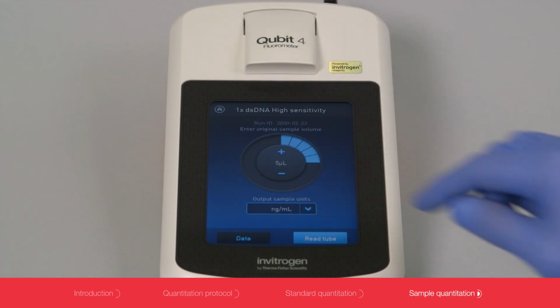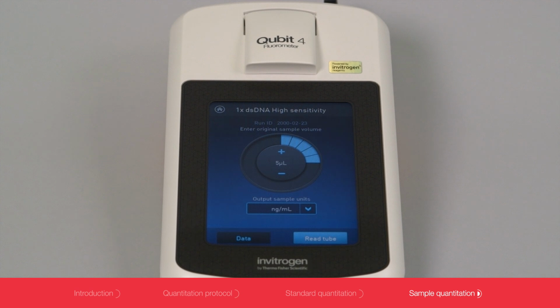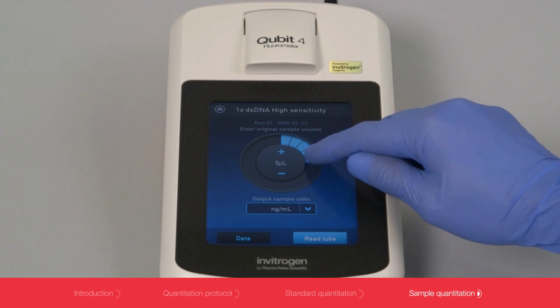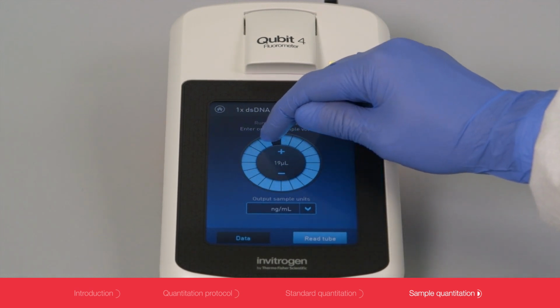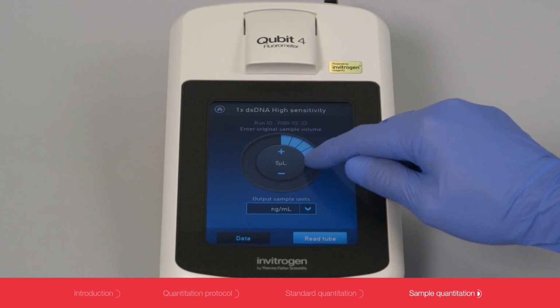After pressing the Run Sample button, a screen will appear that will ask for the amount from your original sample that you added to the assay. This will be between 1 and 20 microliters. You can use the scroll wheel or the plus minus buttons to enter this value.